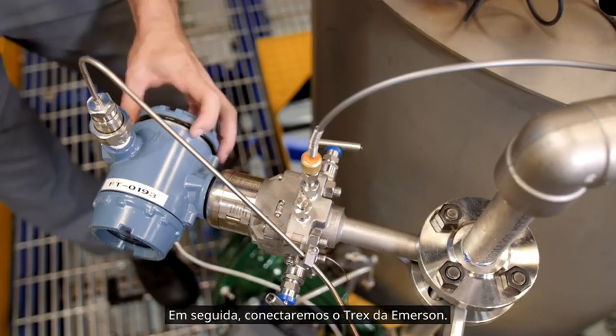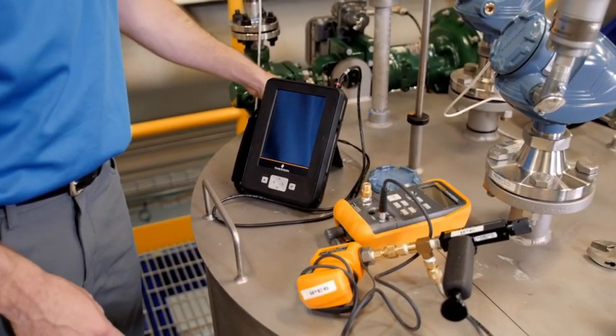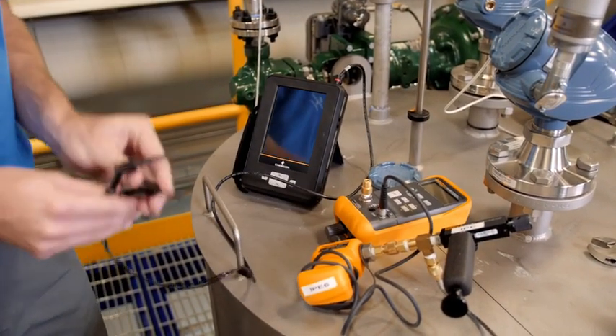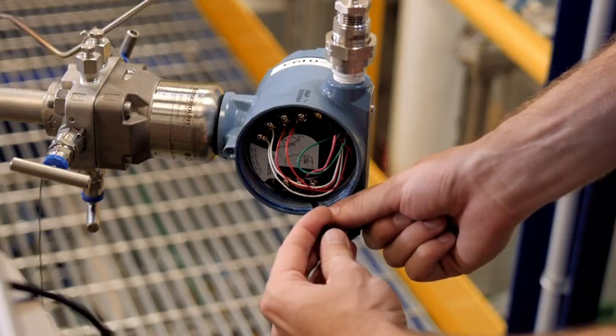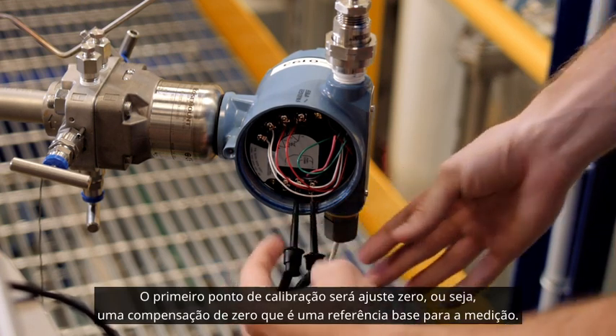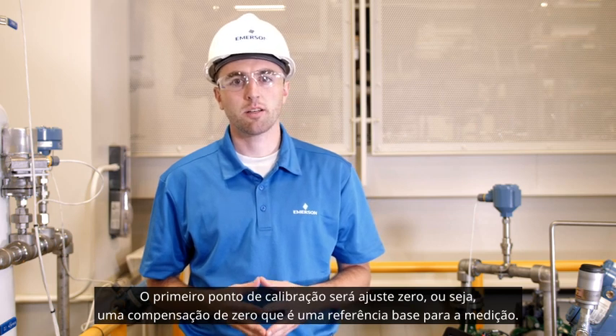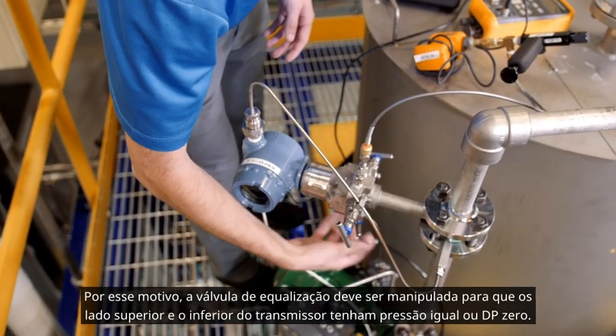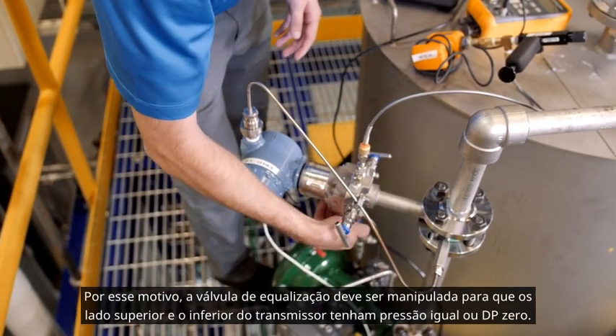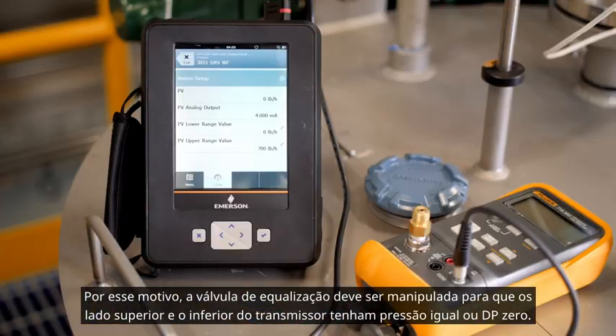Next, we will connect the Emerson Trex. The first calibration point will be a zero trim. A zero trim is a zero-based offset that provides a baseline for the measurement. For this reason, the equalizing valve must be manipulated so that the high and low sides of the transmitter are experiencing equal pressure, or zero DP.